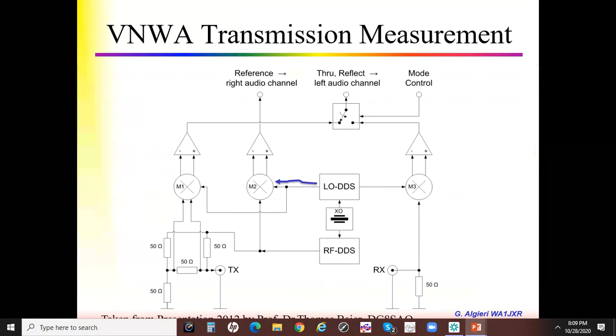If you were doing a transmission measurement, like on a coax cable, an amplifier, or a filter, you'd have a similar process. You still have that reference signal, but now a local oscillator is also sent to mixer number 3. The RF signal goes to the directional bridge and out the transmit port, but now a unit under test is connected between the transmit and receive ports. So the signal goes into the filter, then comes out the other side.